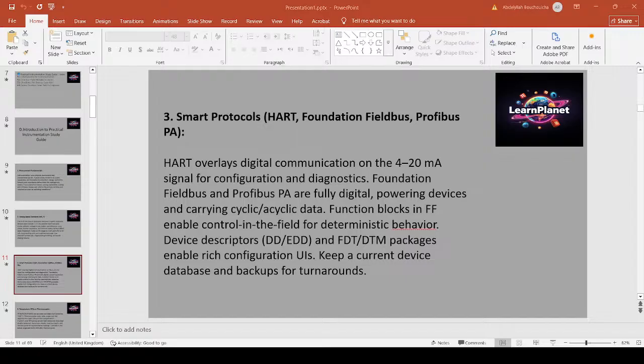HART lets you keep the 4-20 milliamp primary loop while overlaying a low-speed digital channel for device configuration and diagnostics, great for incremental upgrades. Fieldbus FF and Profibus PA are fully digital channels. They can power field devices, carry cyclic data, and allow function block control in the field, enabling distributed control strategies. Device descriptors DD, EDD, and FDT/DTM abstract device specifics for consistent engineering tools. Maintain a device library and backups before turnaround.